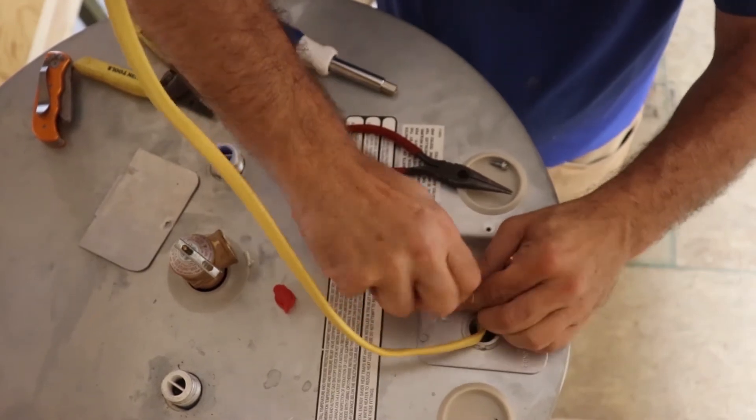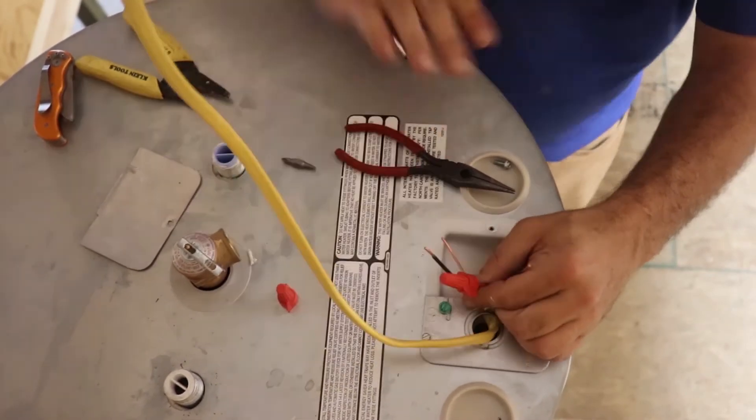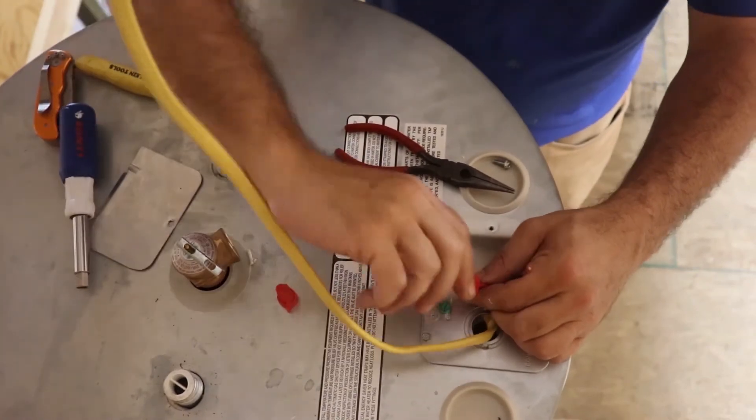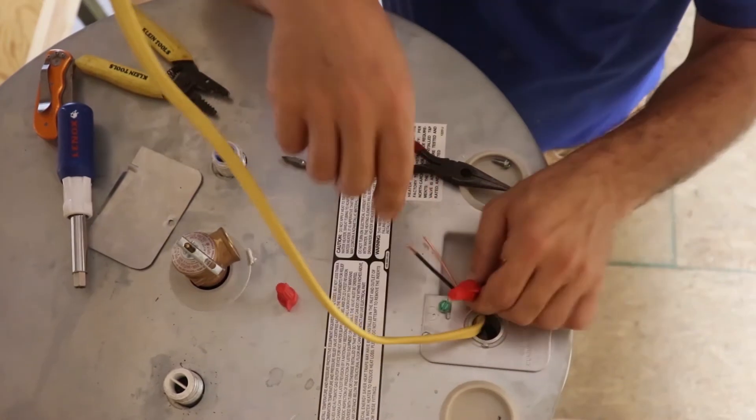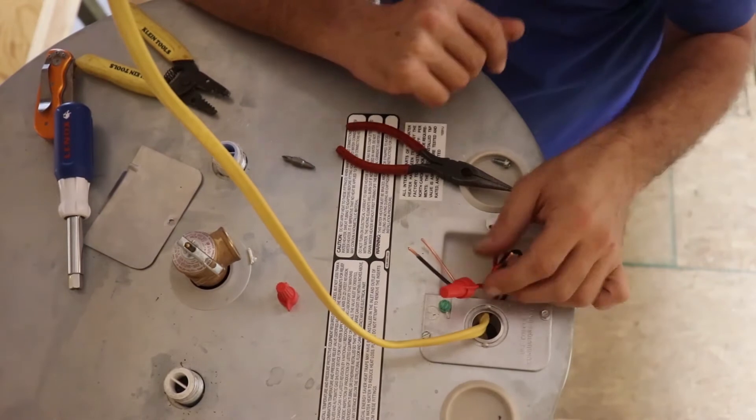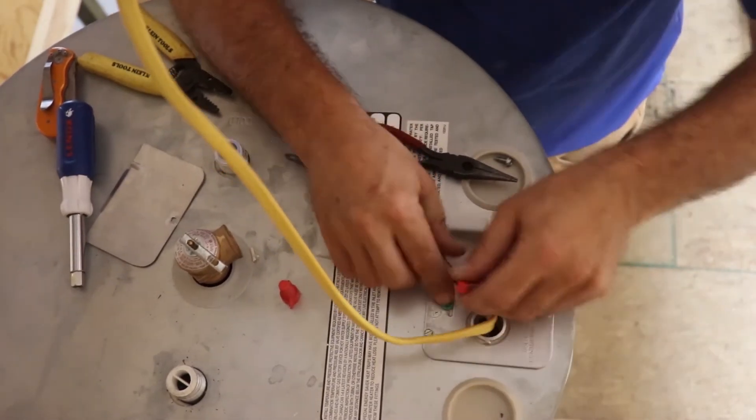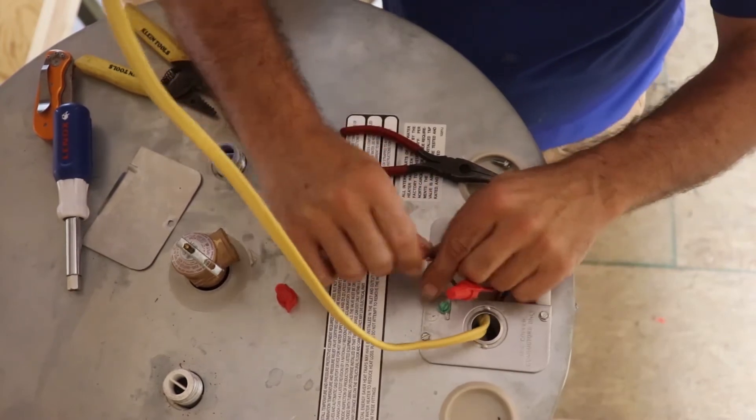And you're going to stick it on there, and you're going to push both of them up in there tight and twist that thing down. Give it good several twists to get it on there. And then what I normally do is I pull on these wires. I pull on that nut and I pull on that red wire, I pull on that white wire to see if they'll come out. If they don't come out, we're good.